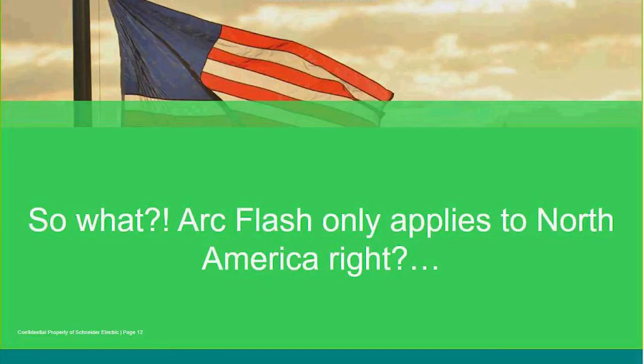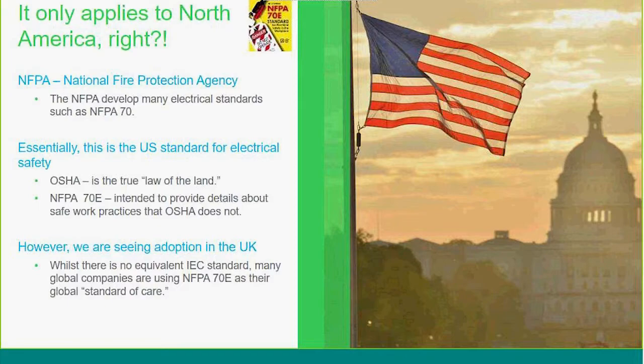So as I mentioned, we talked about arc flash. Most people's view is it's only applicable to North America. And actually, that's very true. The two standards that we talk about are American standards, NFPA and OSHA. But as I've already said, we are seeing some adoption in the United Kingdom, and the Health and Safety Executive are starting to use that phraseology in some of their prosecutions of late, where they're issuing prohibition notices. So understanding the energy levels, understanding the protection on the network, and doing an arc flash assessment is a complementary way of understanding the risk at those points on your distribution network.